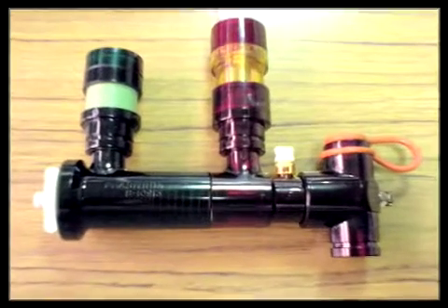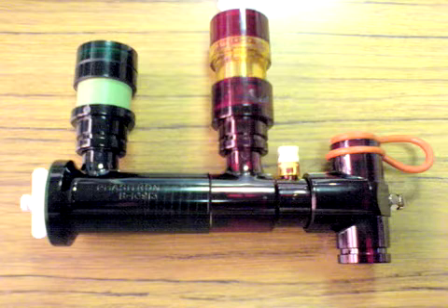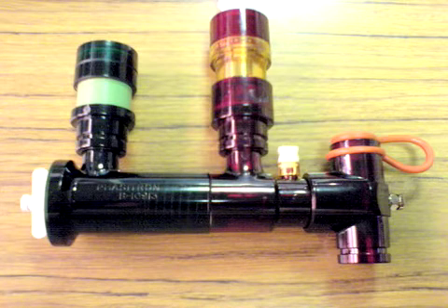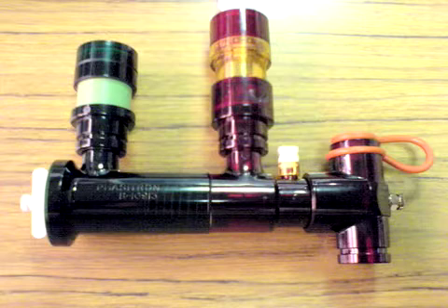This clip covers the Phasitron theory and operation. The Phasitron is a mechanical physiological interface. It is essentially a sliding venturi that acts as both an inhalation and exhalation valve.